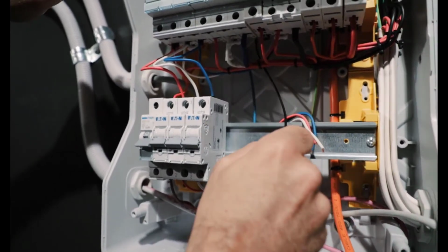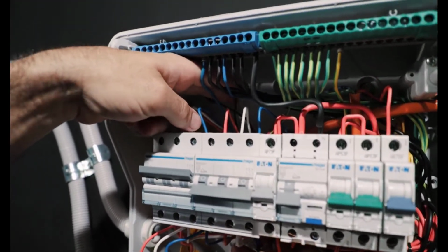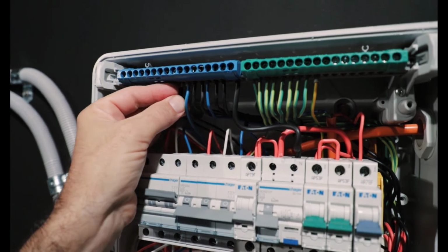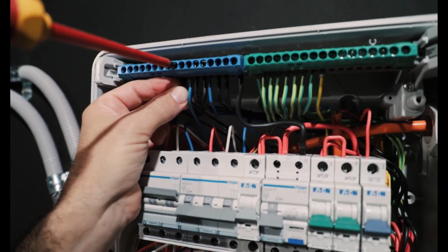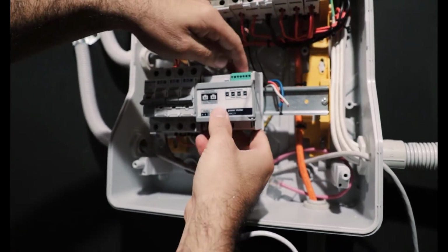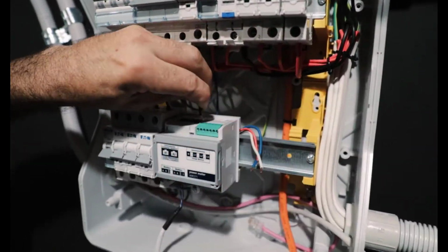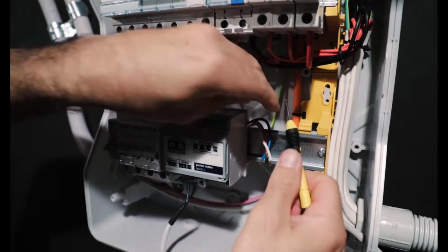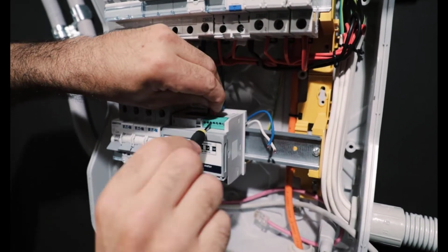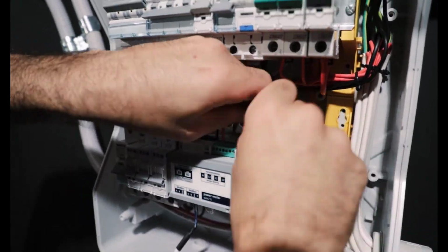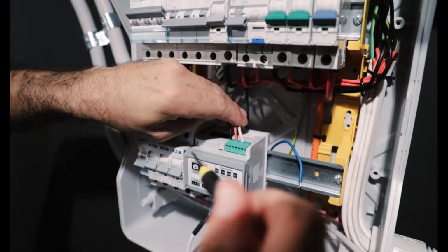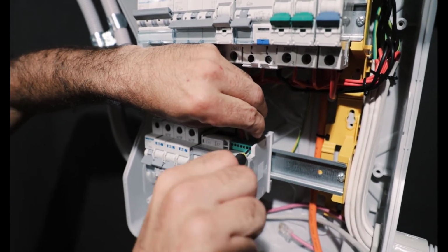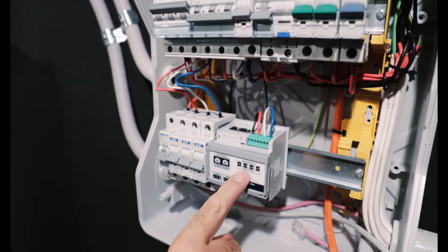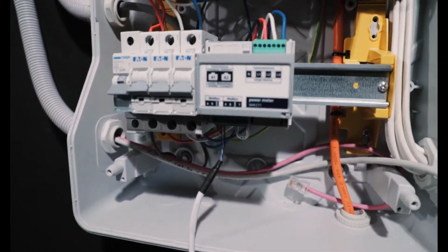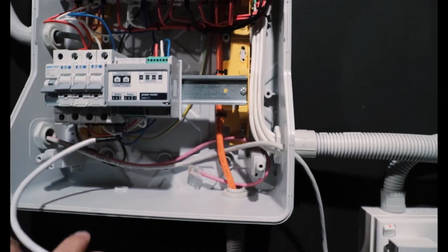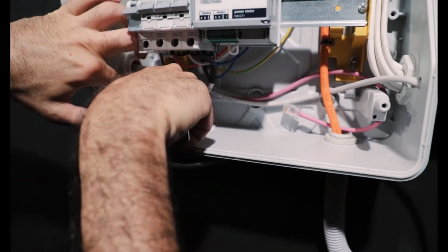Okay, so neutral goes up. Obviously with three-phase installation, we have an awful lot more connections to take care of. Now when we're wiring into a three-phase scenario with the Sonnen system, the meter itself will actually have to be reprogrammed. For that we need an LCD screen, and there's a separate tech note to explain how to go about reprogramming it. For this illustration, what we're actually taking is a three-phase meter, so this one has already been pre-programmed for three-phase configuration.